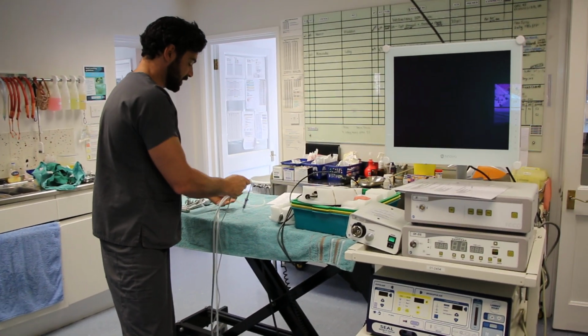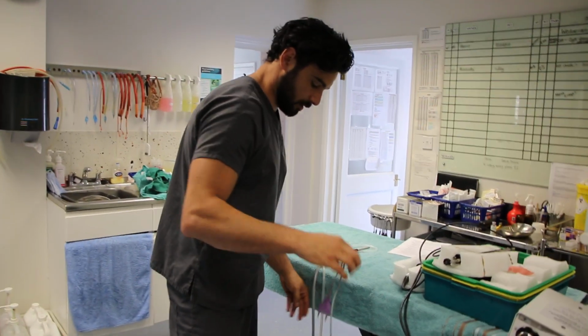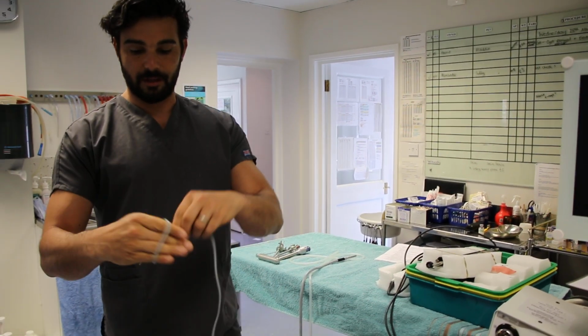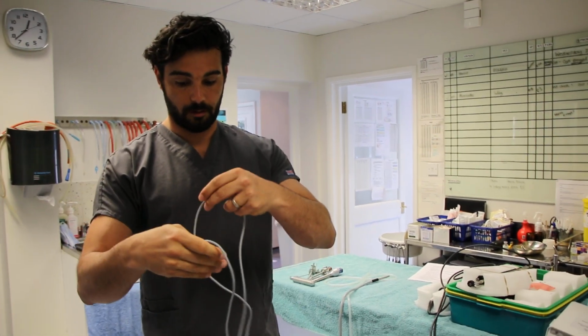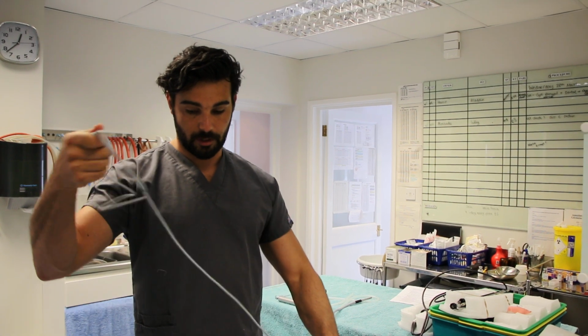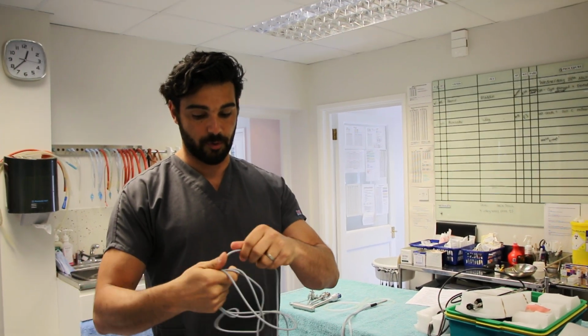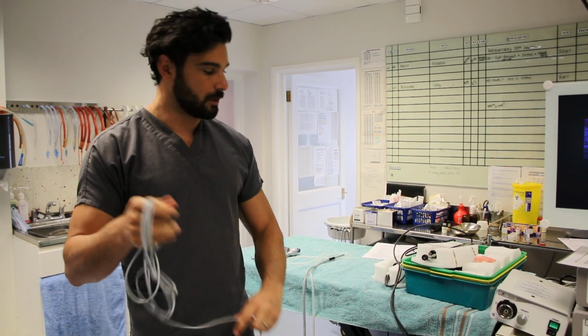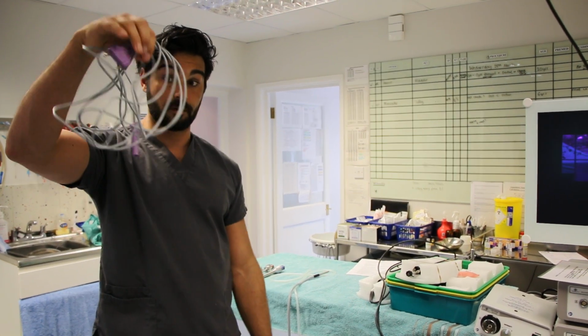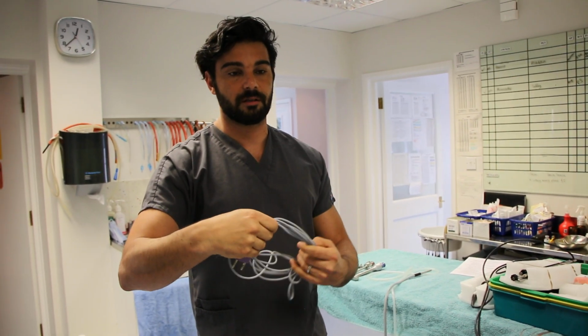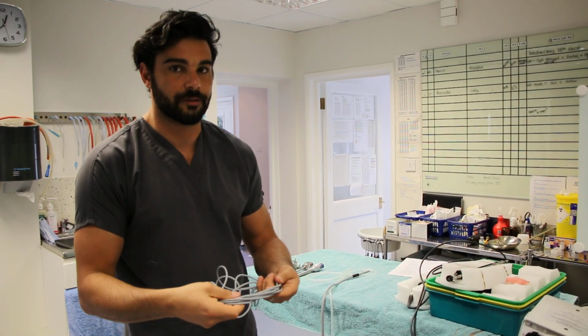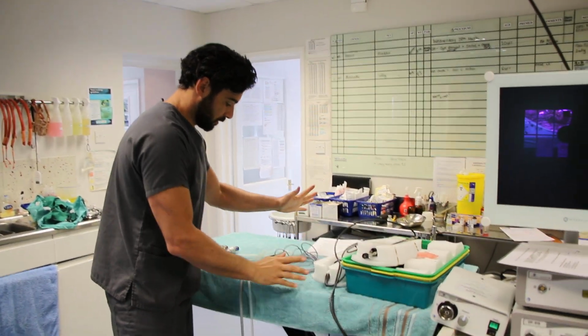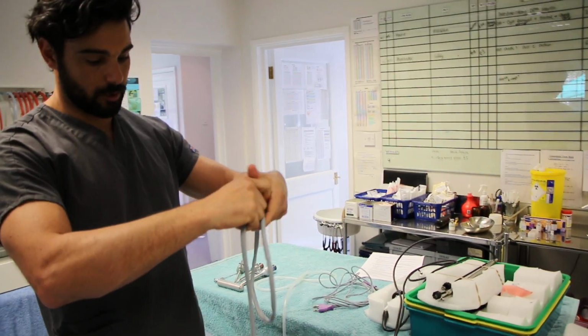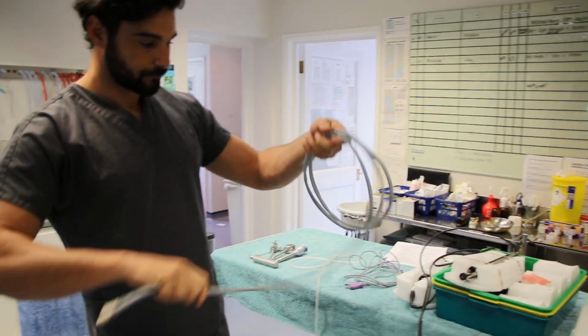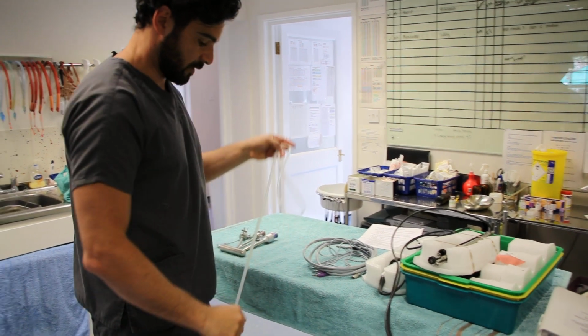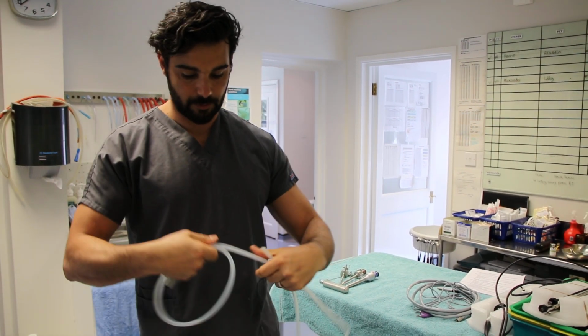It's really important with every single one of these that as they are packaged, they're not looped too tight. So I'd like them in the big bag, if possible, with big generous loops so that the cable is not put under any strain. Just don't underestimate how expensive a stupid piece of cable is, and we need it to last years rather than months, because otherwise it's not cost effective and I'll get in trouble. That's that, again with the cable, nice wide loops. And then with the tubing, similar, keep a similar sort of diameter.